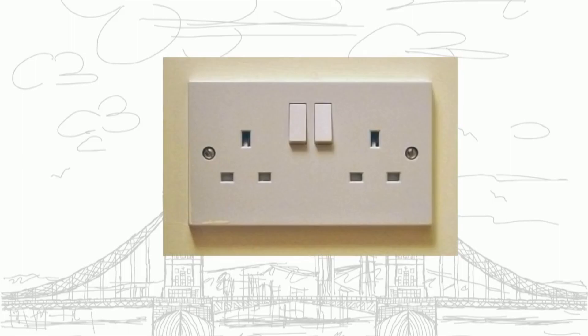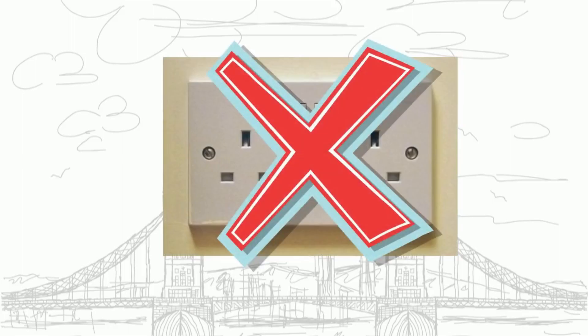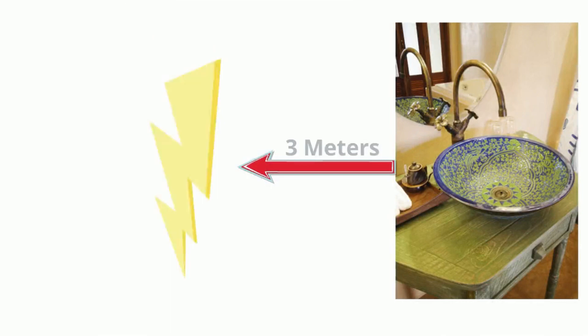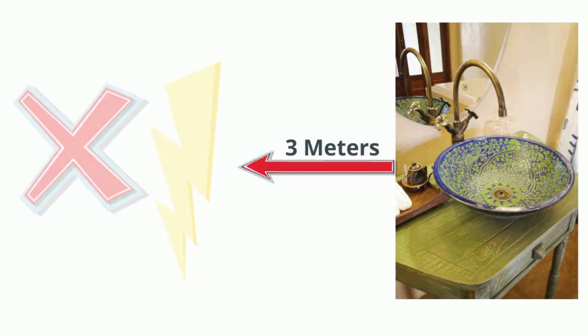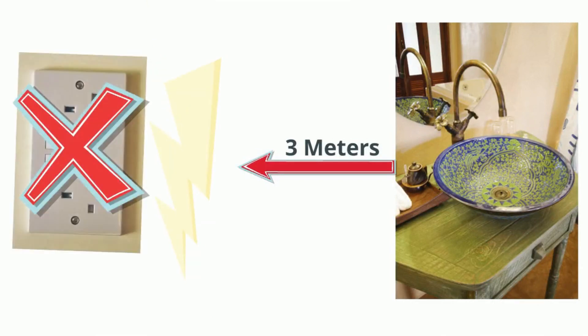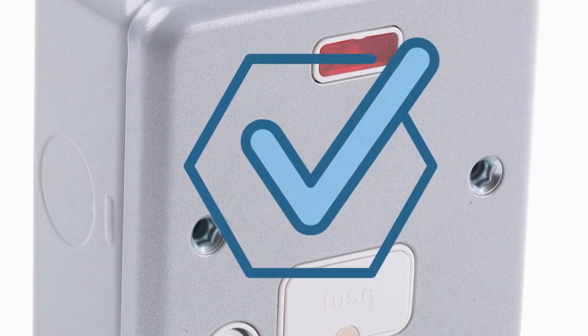Some hand dryers come with a pre-built power plug. However, according to UK regulations, it is advisable not to use a wall plug in the bathroom or toilets, unless you can install them at a minimum distance of 3 metres away from a basin or water outlet. We recommend you fully avoid using a power plug and have an unswitched fuse spur installed with the hand dryer.